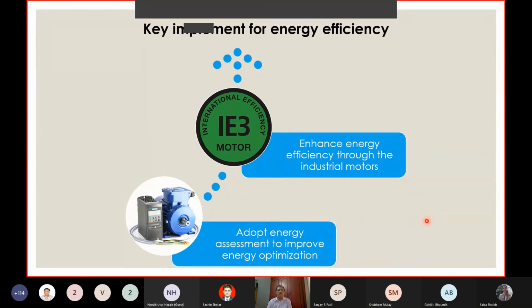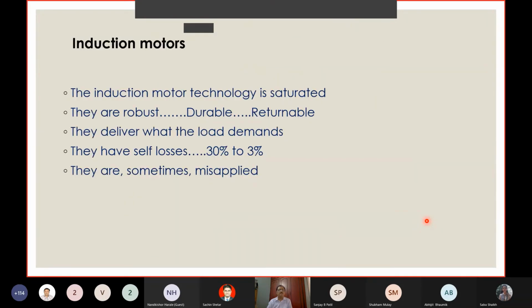And the growth of VFDs is much more than the motor growth year on year, meaning even for existing motors VFDs are being used. One or two words of caution I will add as we go along. Use IE3, use VFD, but when you use IE3 new motors, ensure that the motors are VFD suitable or VFD ready motors. So one commentary on the induction motor. The induction motor technology is a saturated technology. They are robust, durable, and they can be returned after repair or rewinding, which is the normal practice in industries. When you go to the industries, you will find that this is what is normally happening.